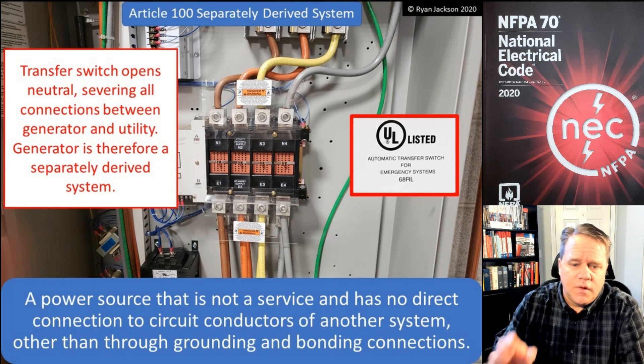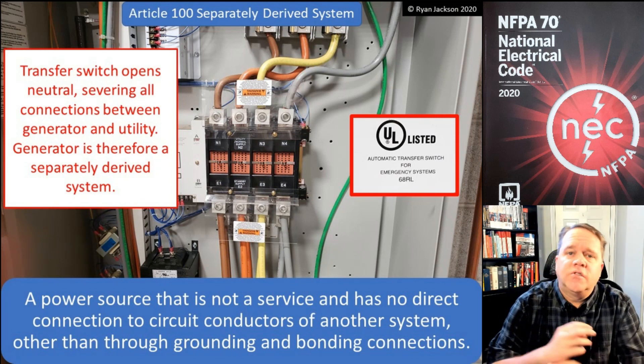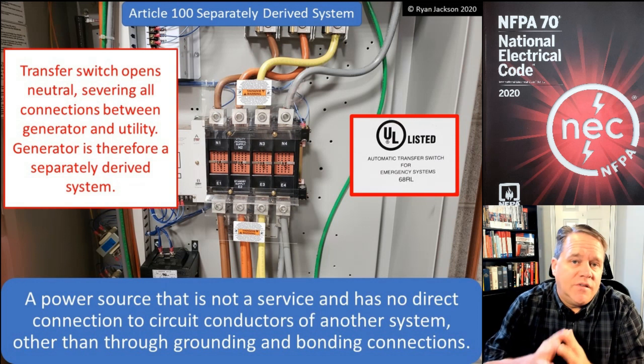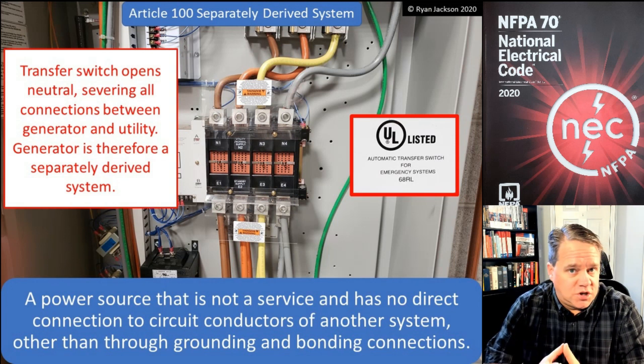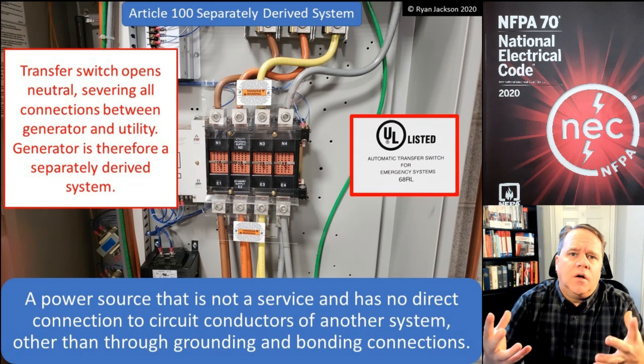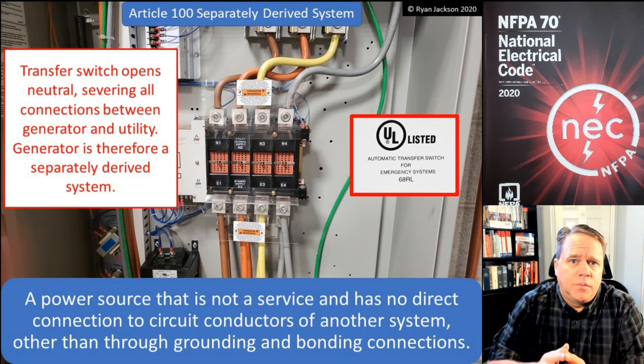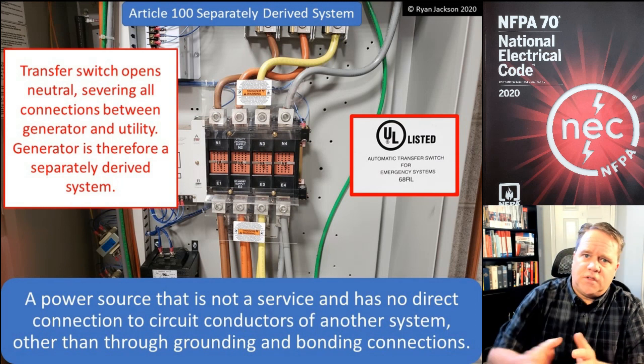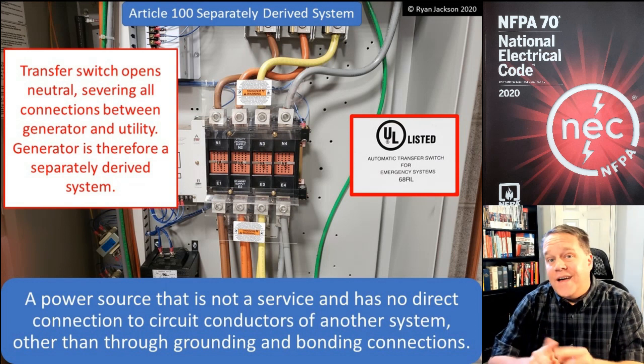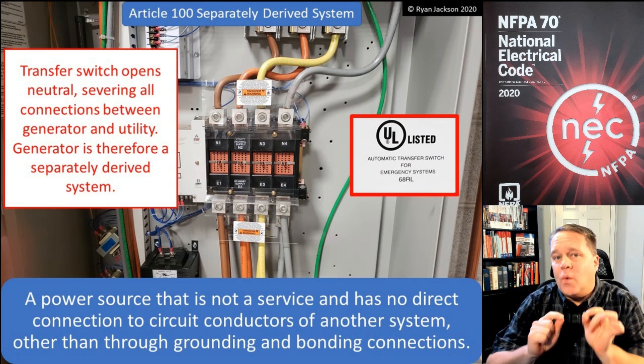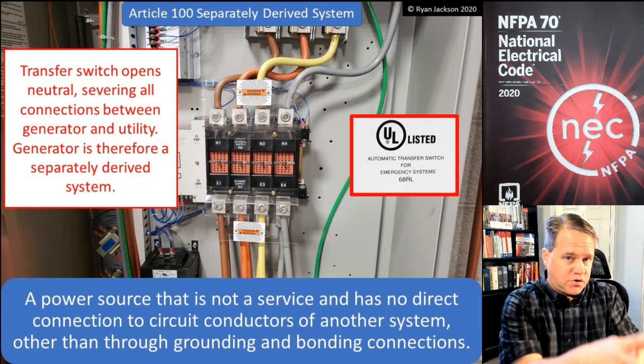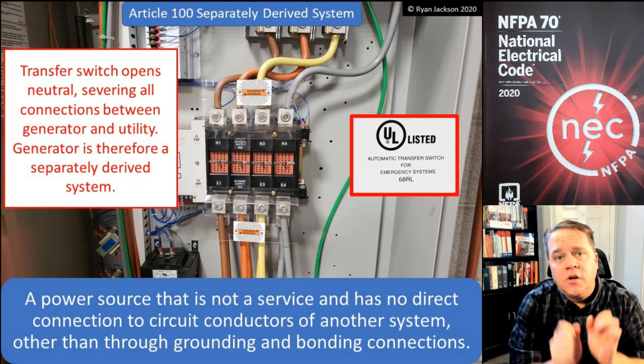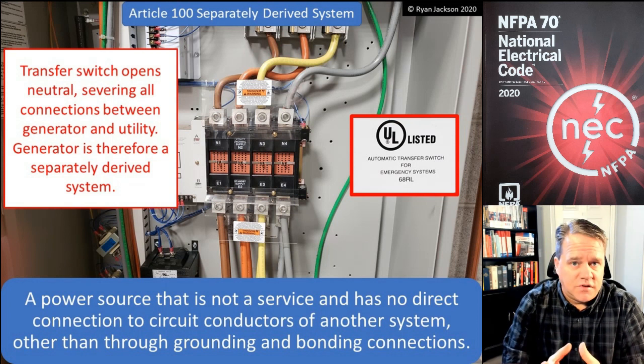What about a generator — is that a separately derived system? The answer is: sometimes. But here's what's important: it has nothing to do with the generator itself; it has everything to do with the transfer switch. When inspecting large commercial projects, I'd stop electricians from showing me the generator first, because I can't know how to evaluate the generator until I've looked at the transfer switch. The transfer switch determines whether or not the generator is a separately derived system.